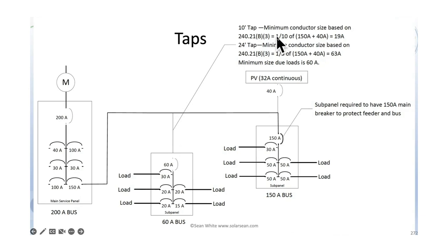If it was the 10-foot tap rule, if it was only 10 feet or less, then this conductor would only have to be 19 amps. And obviously with a 60 amp breaker, it already has to be greater than 19 amps. And so those are the tap rules.